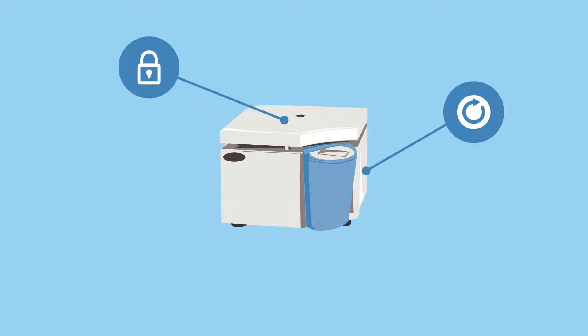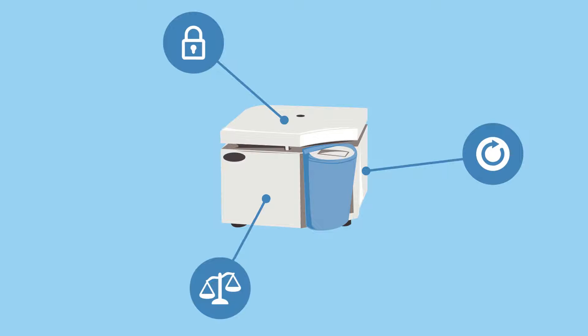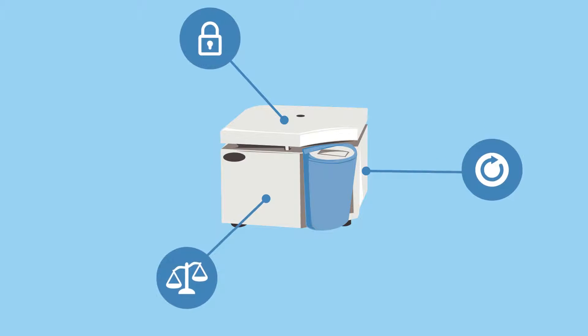Safety is always important in the lab. Linda wants to look for a centrifuge with a variety of safety features, including a safety-lock lid to keep users safe during operation, automatic rotor identification to ensure that rotors cannot achieve speeds higher than their intended use, and imbalance detection, which will automatically stop the motor in the event that excessive vibration is detected.